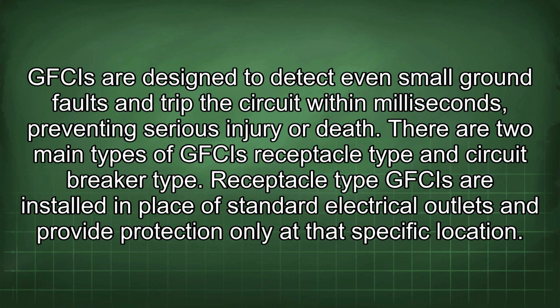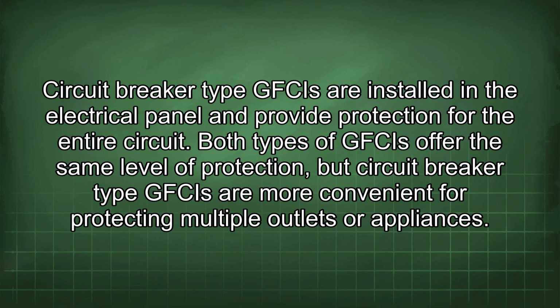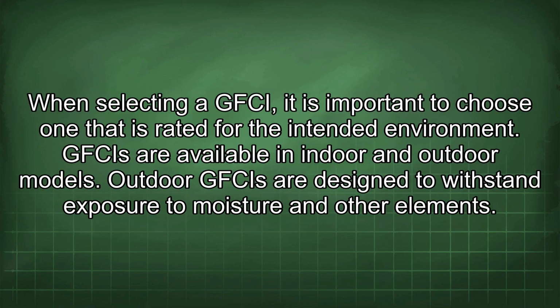There are two main types of GFCIs: receptacle type and circuit breaker type. Receptacle type GFCIs are installed in place of standard electrical outlets and provide protection only at that specific location. Circuit breaker type GFCIs are installed in the electrical panel and provide protection for the entire circuit. Both types of GFCIs offer the same level of protection, but circuit breaker type GFCIs are more convenient for protecting multiple outlets or appliances.